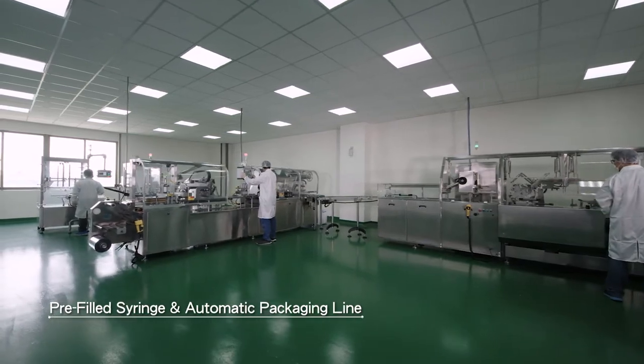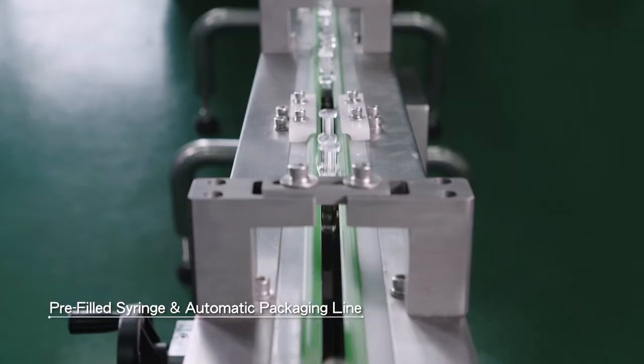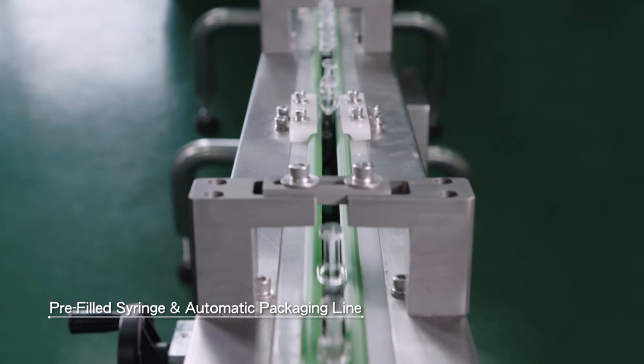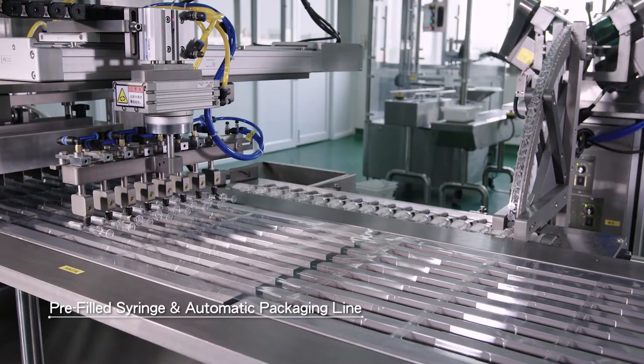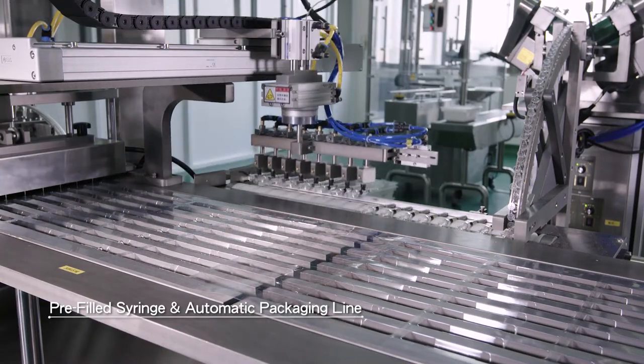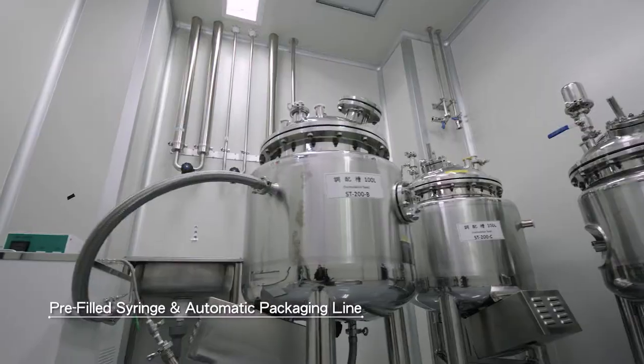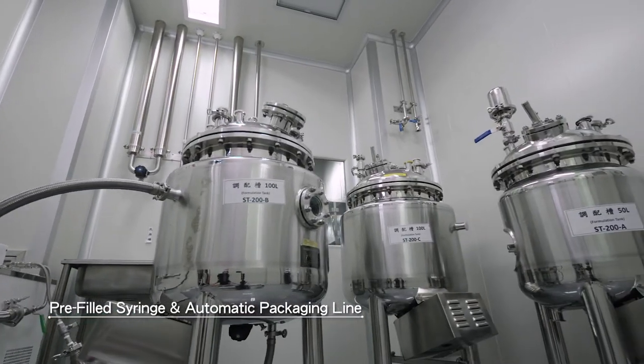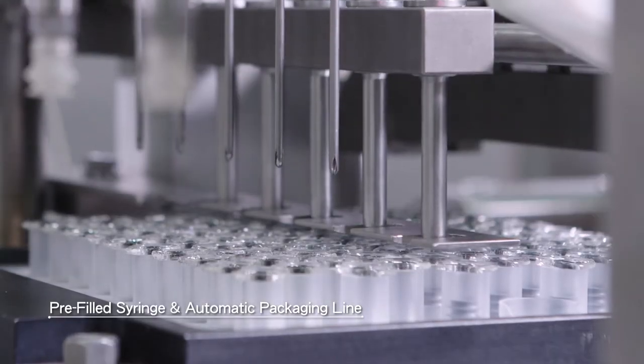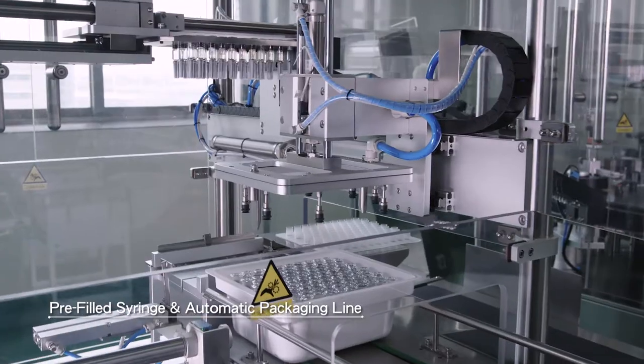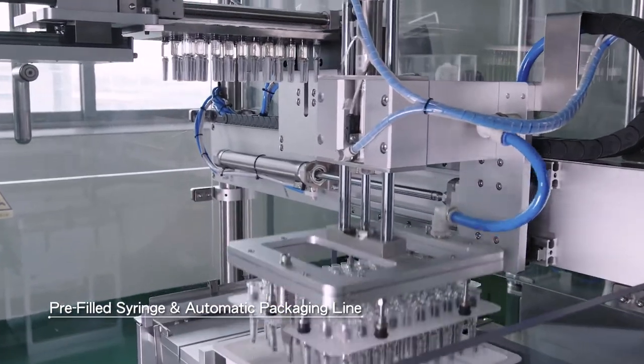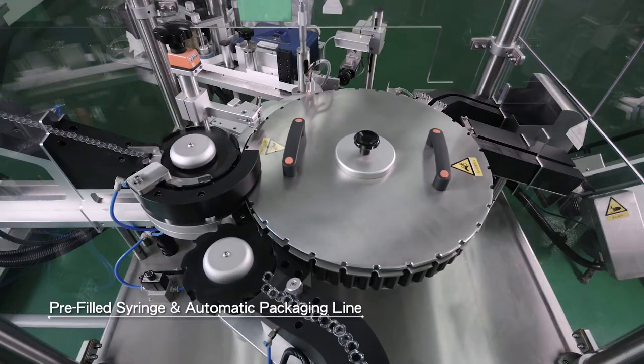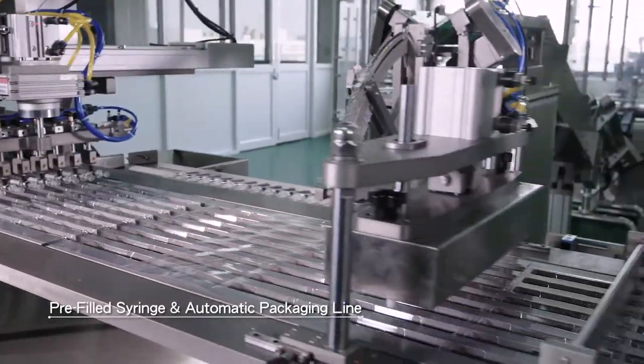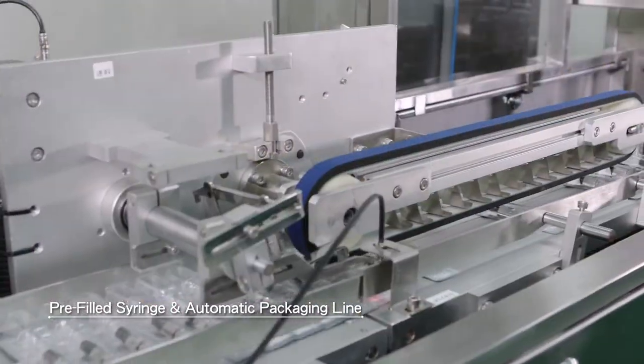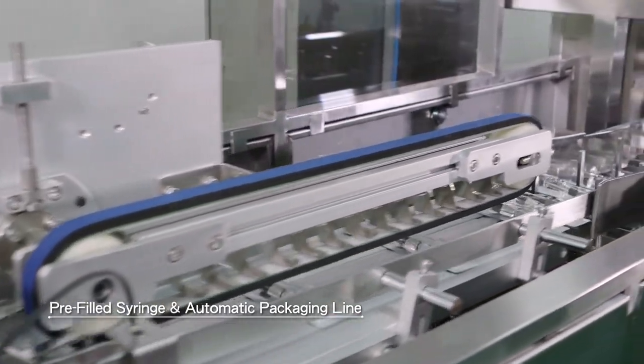Single-chamber or double-chamber prefilled syringes or injection pens can be manufactured in the prefilled syringe line and the automatic packaging line. The annual capacity is up to 12 to 16 million. Procedures cover compounding, sterile filtering, automatic filling, stopper sealing, inspecting, automatic nest tub unloading, plunger rod screwing, labeling, blistering, and packaging.